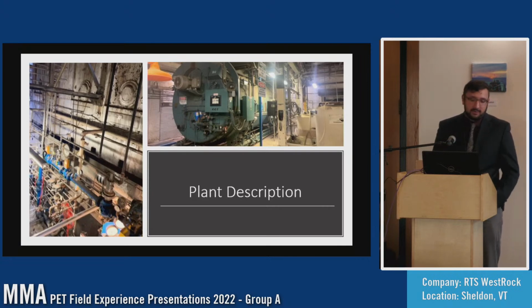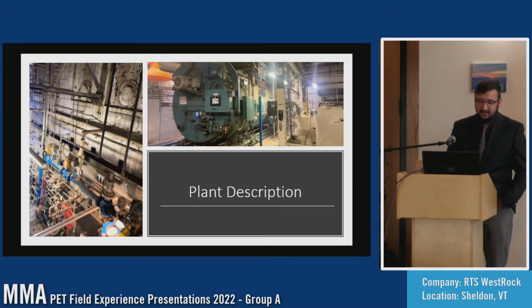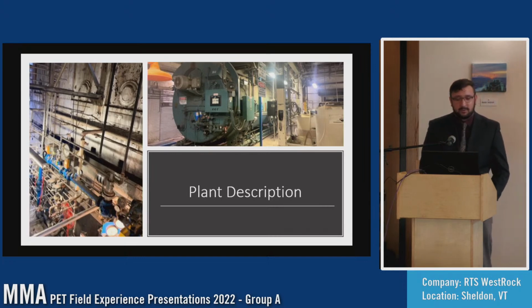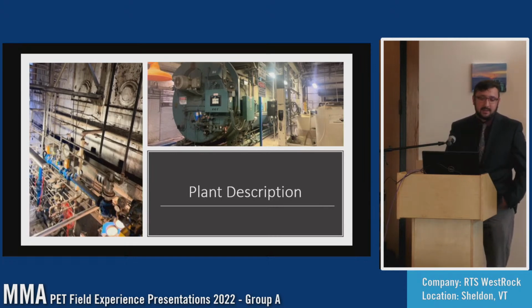At the mill we have 4 different boilers. One is a 1952 Wickes water tube boiler that runs at 600 psi superheated steam, then it is desuperheated, and there's a PRV that brings it down to 165 pounds before it goes into the system. Number 2 is a 2008 Cleaver Brooks fire tube package boiler, which also runs at 165 pounds. Boilers 3 and 4 have a common wall - they are a 1923 Babcock and Wilcox boiler, and they run at 165 pounds.